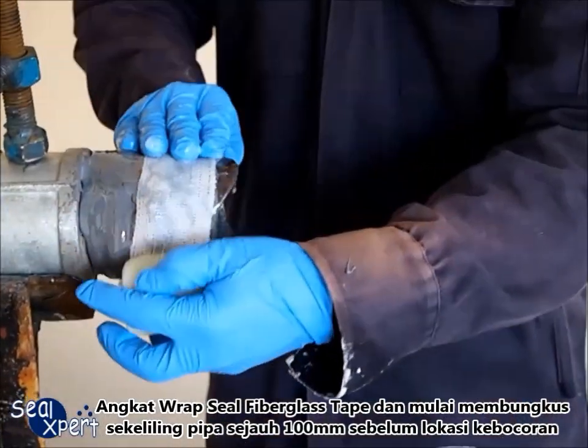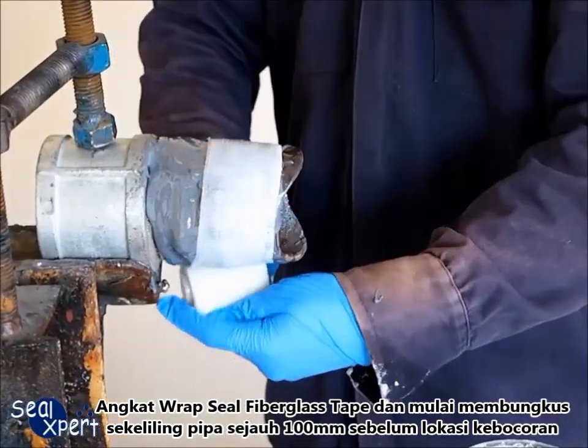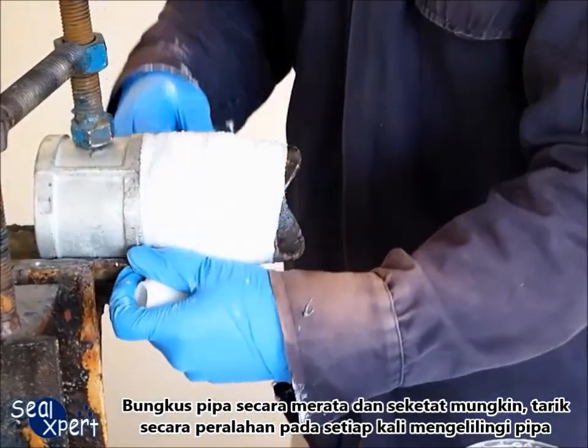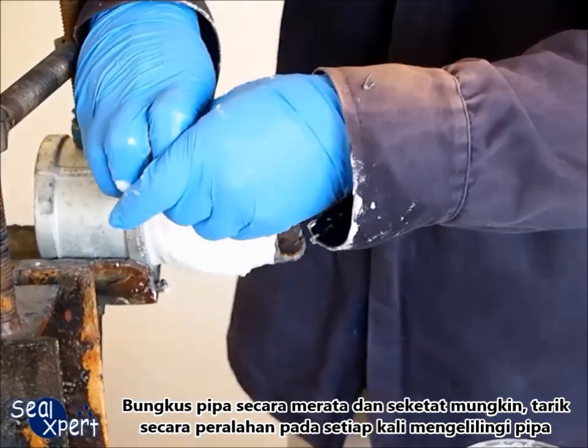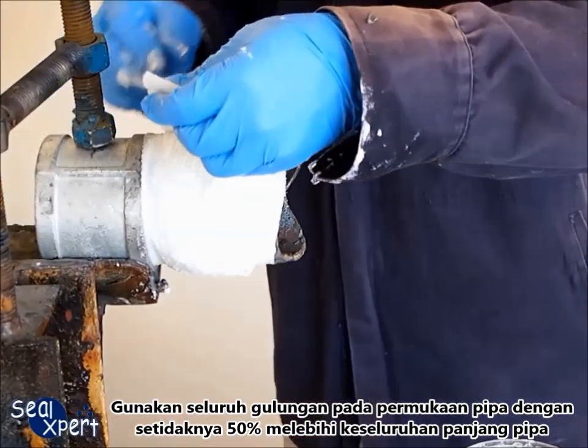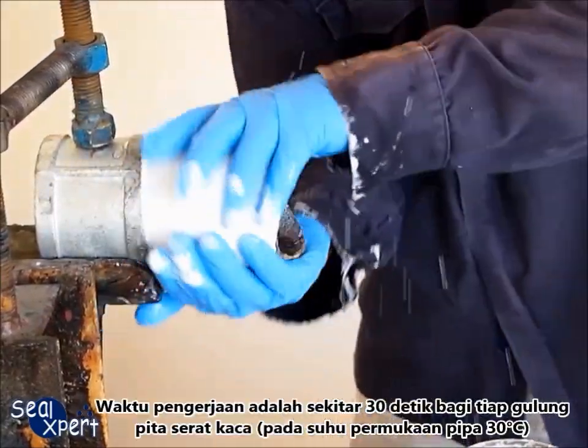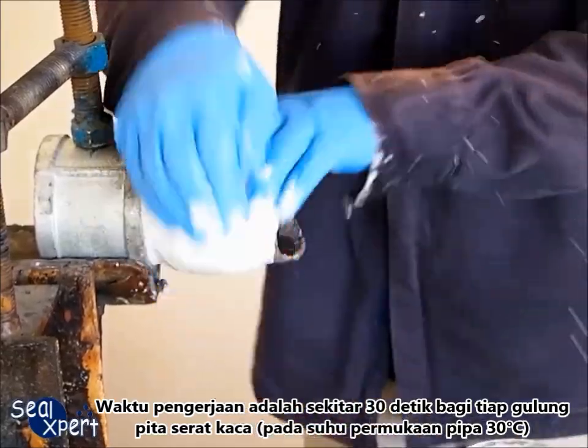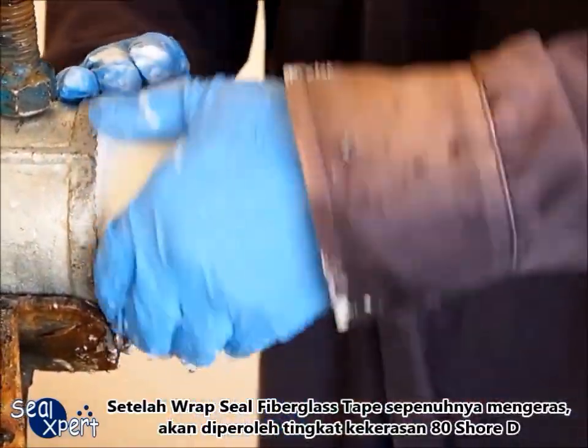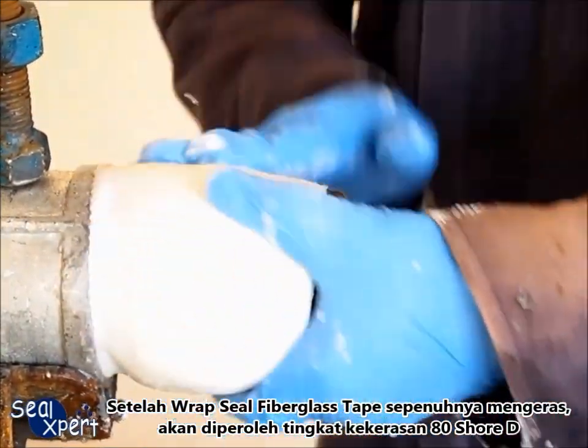Pick up the wrap seal fiberglass tape and start wrapping around the pipe at about 100mm before the leak location. Wrap the pipe as evenly and as tightly as possible, pulling slightly after each round of wrapping. Apply the entire roll over the pipe surface with at least 50% overlap for the entire repair pipe length. The working time is approximately 30 seconds for each row of fiberglass tape at 30 degrees pipe surface temperature. After the wrapped seal fiberglass tape is fully cured, it will attain approximately 80 Shore D hardness.